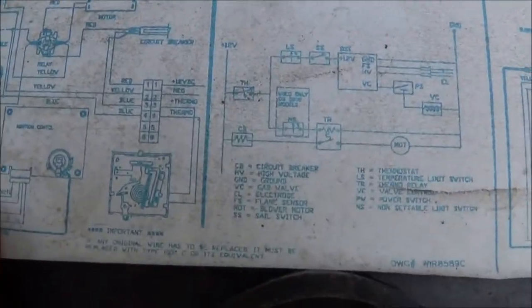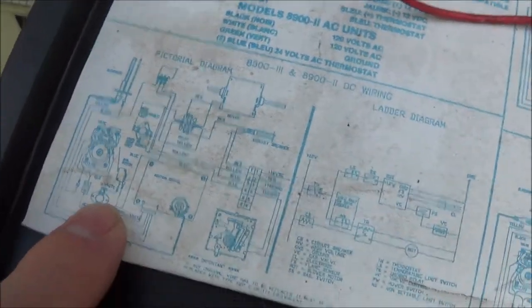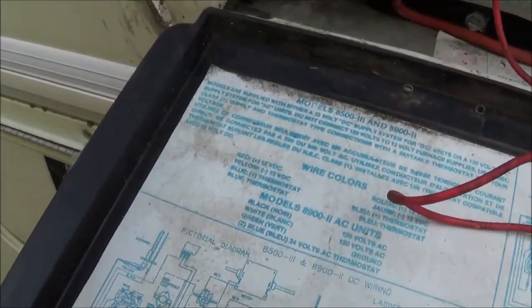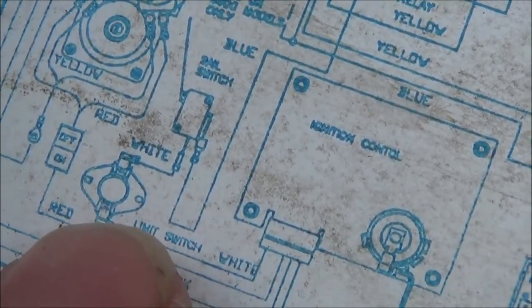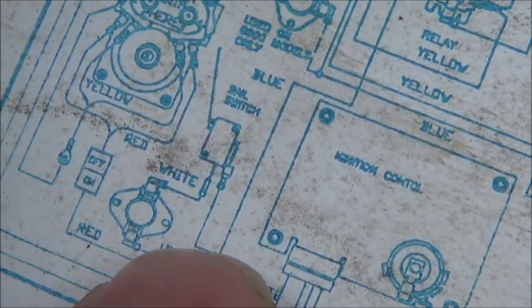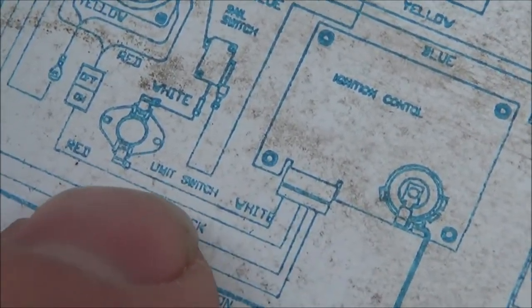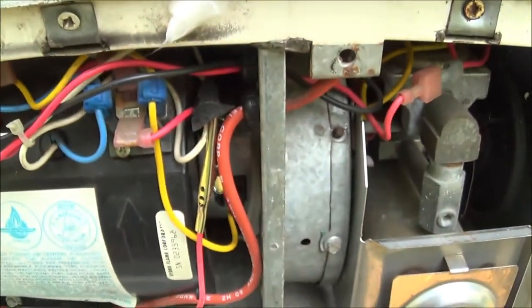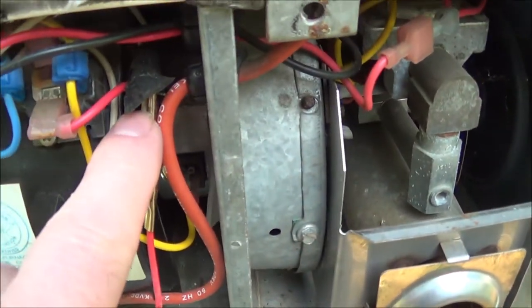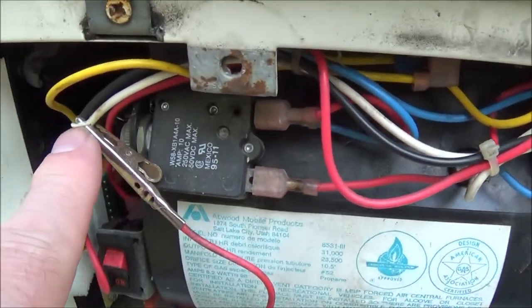So I bypass from here on the input of the sail switch to here on the output of the high limit switch. On the rig, what that looks like is: shave the wire — the white wire here — and use a jumper with an alligator clip over to the white wire at the output of the high limit switch.